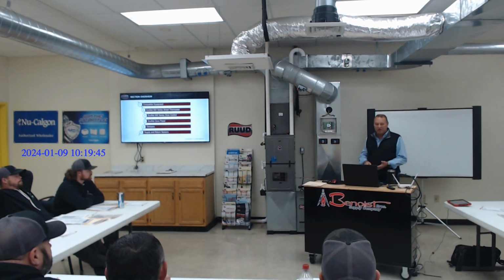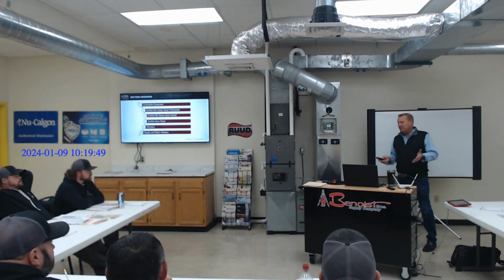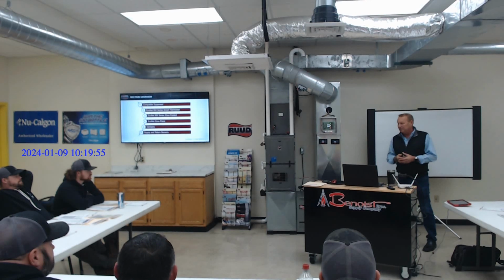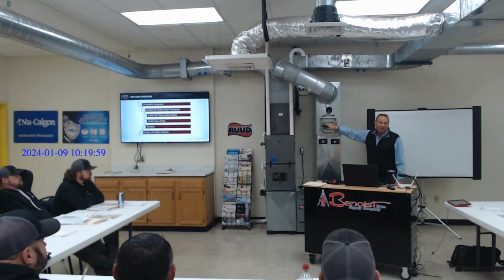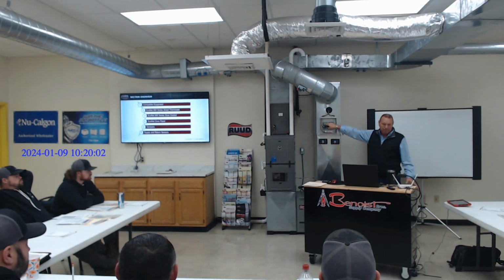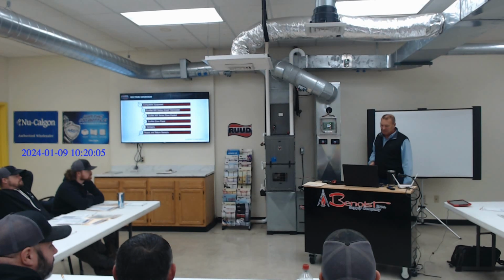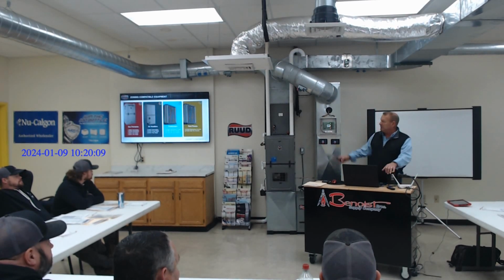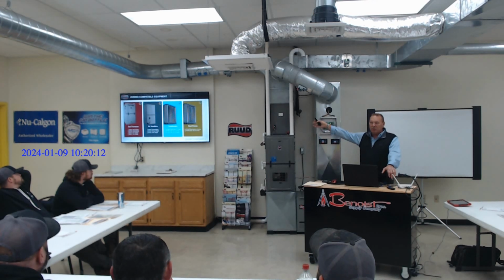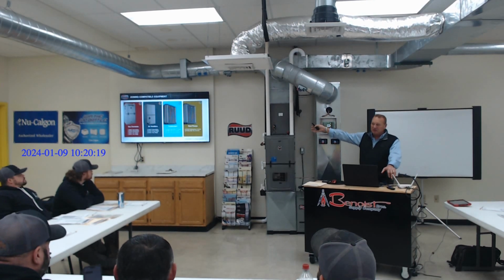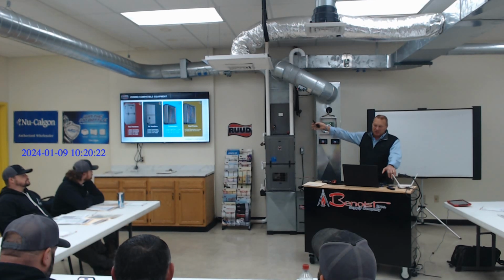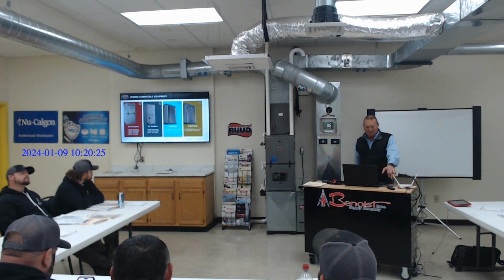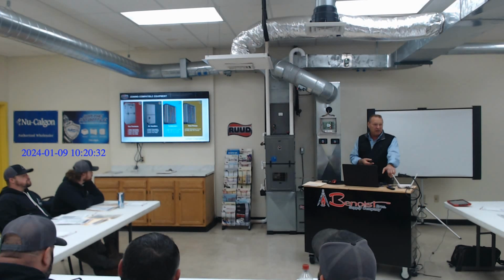Because when I communicate, if you guys all put in some communicating equipment, it's R, C, E1, and E2, right? Everywhere, unless I have a non-communicating outdoor. So I have to have RC and E1 and E2 bridge coming into this control panel. Okay? Does it make sense? Again, here's the equipment. I just showed you, struggled through it, but where to find the equipment you can communicate with and zone with ECONET zoning. All the other stuff you can zone traditionally if you want to. But the communicating equipment, you want to zone with the ECONET zoning because you have a lot more liberties of setting up airflows and things with the ECONET zoning.